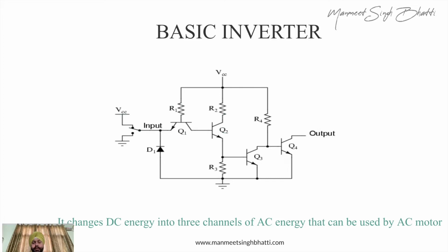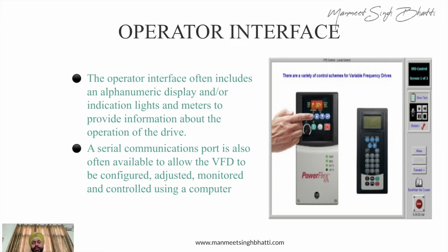Then is the basic inverter. It's a standard inverter where the DC power fed from the rectifier section is converted to AC. It's the same kind of inverter we use in our homes, but it's a three-phase inverter now. It gets a DC input, and based on the DC input, it gives an AC output. We control the output circuit, where the switching happens. It is always on-off switching, where you get a complete waveform in a similar fashion, so you are getting the AC waveform. So in the beginning we converted the AC to DC, we smoothened the curve, and then again we converted to AC. Here we have control of the switching, so here we also control the frequency. Based on that frequency, you are able to control the power.